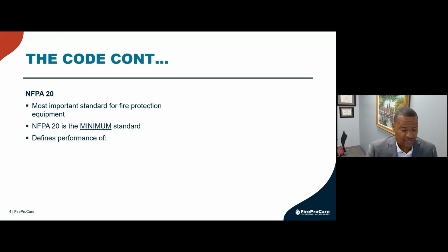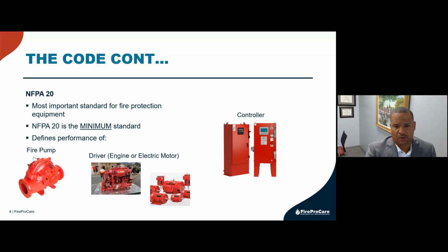It is the most important standard for fire protection, in my opinion. It is a minimum standard. So if you have a local jurisdiction that has something in place that actually goes above and beyond NFPA 20, there's nothing wrong with that. The key is to make sure you understand NFPA 20 is the baseline for the design of the fire pump controller. And I think it's important because it defines the performance of the fire pump, the driver, which will be your engine or electric motor, as well as your controller. And that's all included in this small publication, NFPA 20.